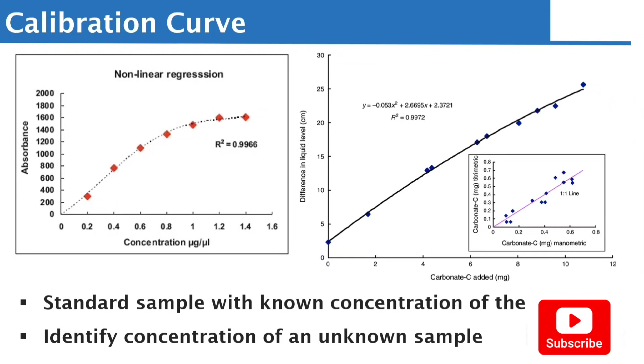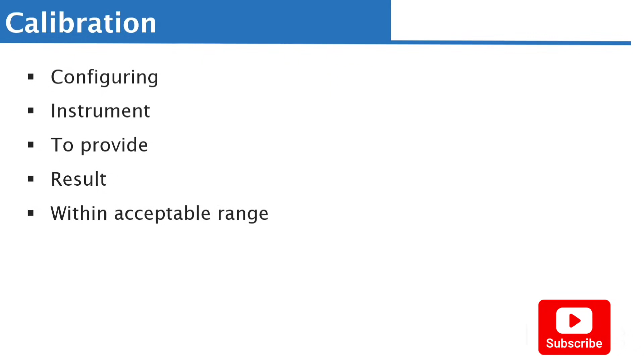I have spent time here to explain this because it is important we understand what calibration means. Now, what then is calibration? Calibration is a process of configuring instruments to provide results within an acceptable range. So you can see the words have come again, acceptable range. That acceptable range is a range generated by that calibration curve. So calibration is a process by which we configure, we adjust the instrument to be able to provide a result that is within the acceptable range. And like I said, that acceptable range is a range generated by the calibration curve. I hope that makes sense.